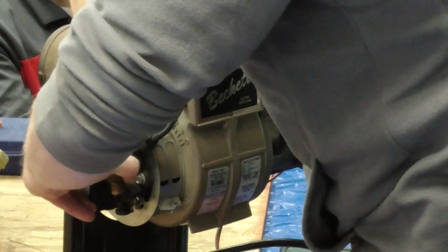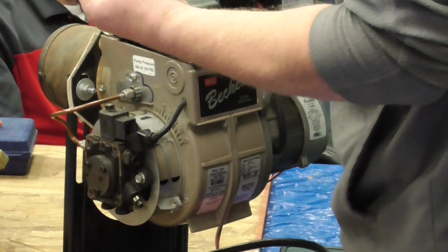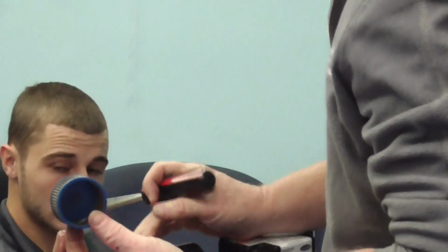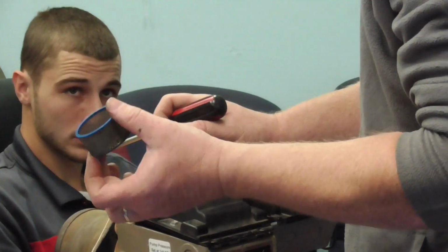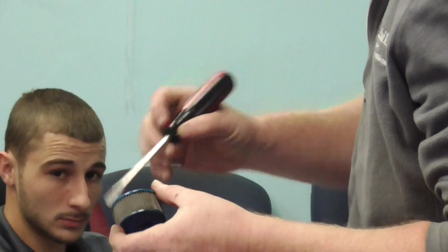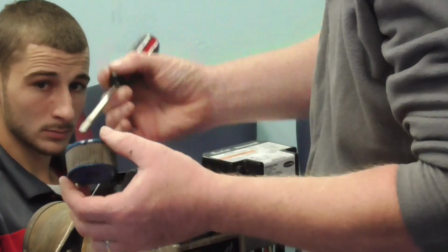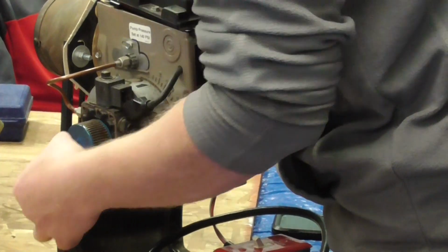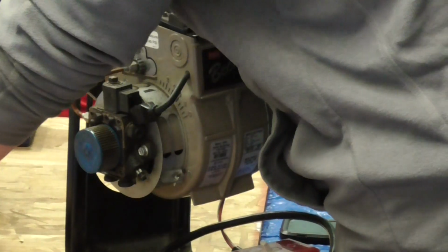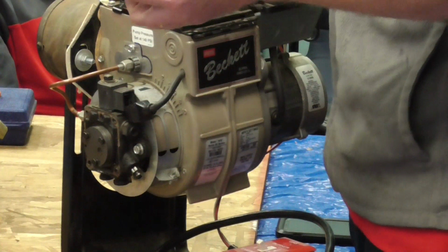And this is why I covered this table. But they go this way. Inside of here is your last line of defense. If you've already checked everything else, these will clog up. You should have contact cleaner in your truck, which is basically glorified brake clean. It'll blast these things right out. Contact cleaner, degreaser, anything, just spray it from the inside out. And it'll just blast the heck out of these things.